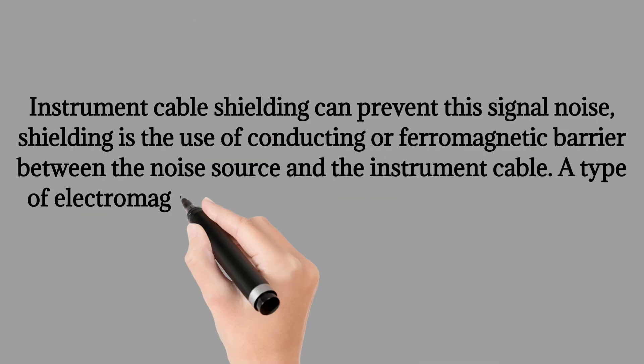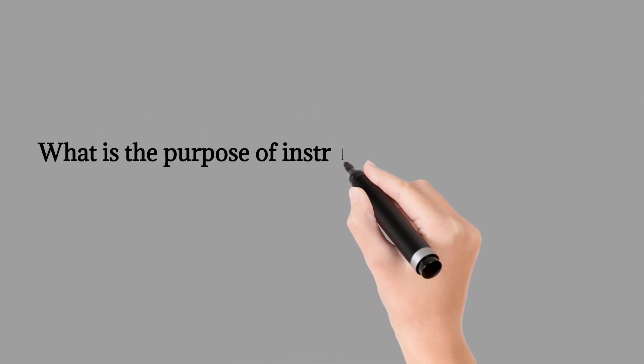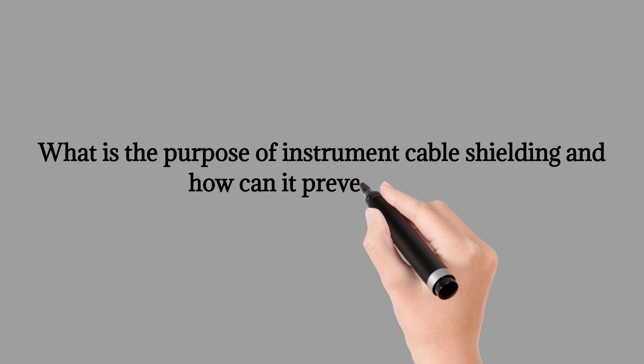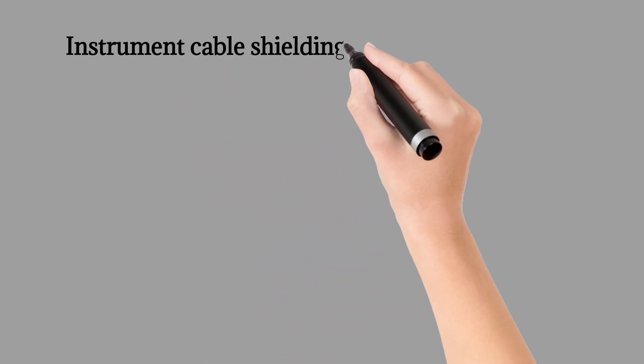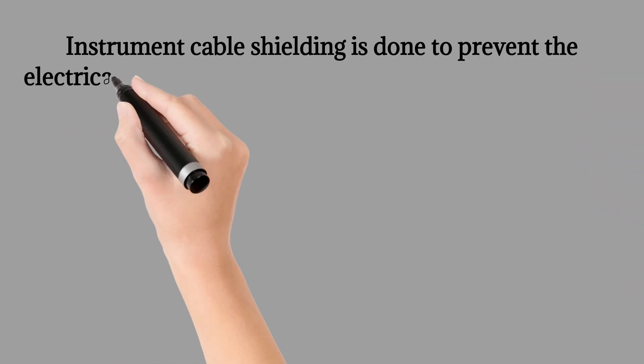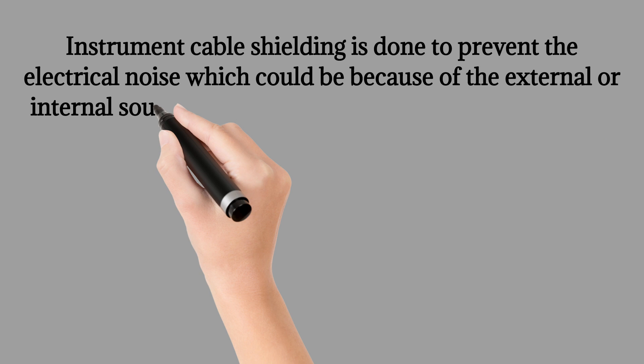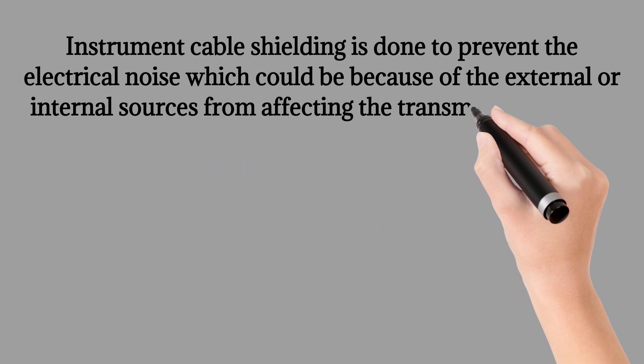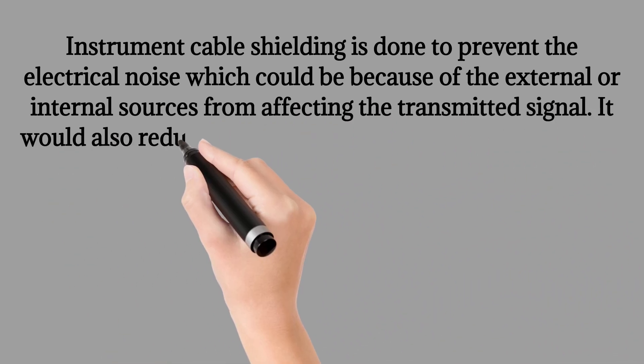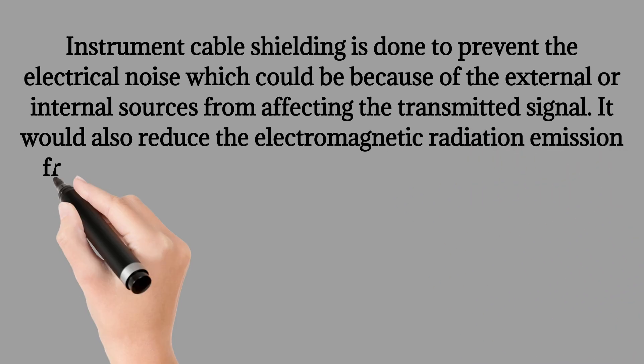Instrument cable shielding can prevent this signal noise. What is the purpose of instrument cable shielding and how can it prevent noise? Instrument cable shielding is done to prevent the electrical noise which could be because of the external or internal sources from affecting the transmitted signal. It would also reduce the electromagnetic radiation emission from the cable itself.